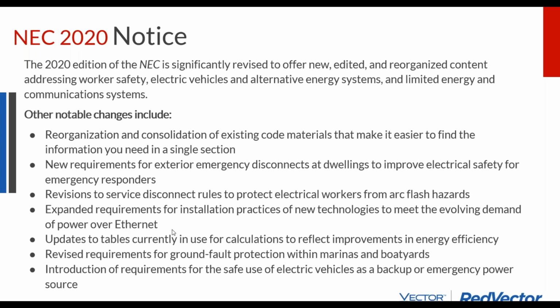Some additional requirements for Power over Ethernet devices. That's a specialty section towards the back. One we'll reference in class today is that the load calculation charts have finally been updated for LED lighting. And so there are minimum loads that you have to design a building and a power system for, found in code. Incandescents and LEDs have a 90% difference in energy efficiency. And so these tables have finally kind of been drawn back to say we can design the footprints of buildings to have less energy demand because of the reduction in lighting load.